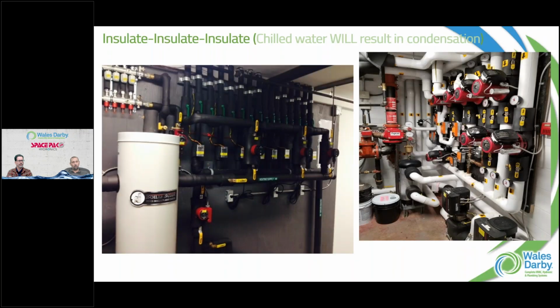This one, again, we talked about insulation - two perfect pictures here, one with fiberglass insulation with that hard shell, the other maybe a foam. But it doesn't matter where that pipe's going or if you think nobody will see it - if it's metallic, it needs to be insulated. Handles, valves, even around the circulator bodies, all need insulation so there's no exposure to humid air, so you're not rusting out the stuff. We've seen that happen in the past.